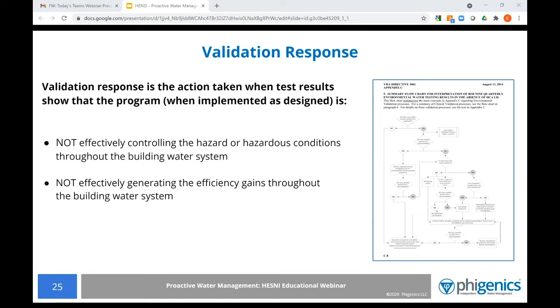If you're validating your water management program, the program should have a defined validation response, or the actions you take when the test results come back positive and show that the program is not effective. This is typically represented through what we call a validation response guide, and an example is shown on the screen. The purpose is to provide the team an algorithm to follow for remediation of those positives and next steps if needed. This isn't a core document of the water management program, but it supports the validation step.